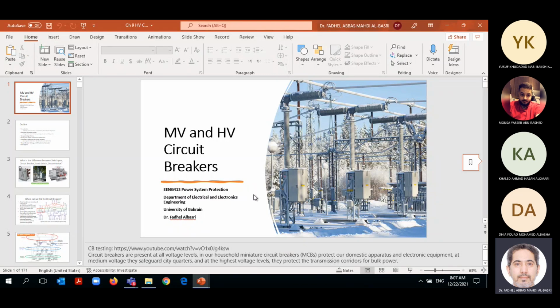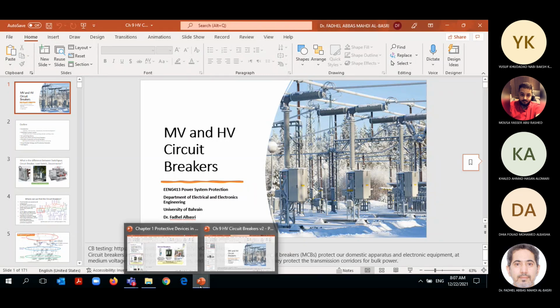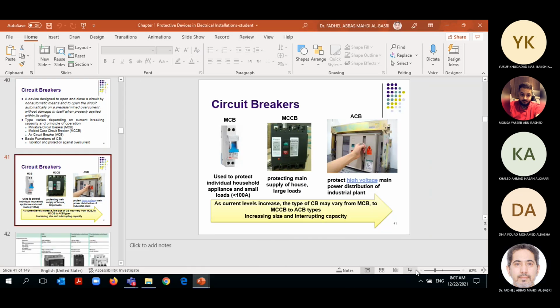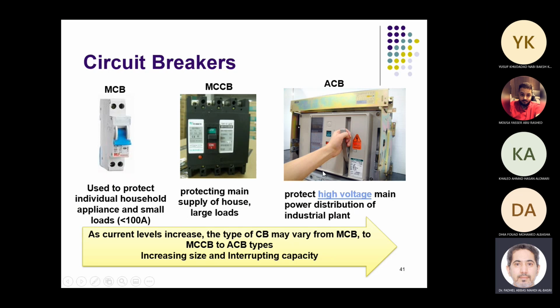So I'll not look at the breakers that are at home, like these ones. These are the breakers at low voltage systems. They classify them from low: MCBs, which we call miniature circuit breakers. Miniature means small breakers, and these breakers are normally rated up to, let's say, 100 ampere. This is for household circuit protection, and you'll find it in a distribution board that I'll show you later. Their breaking capacity, the maximum current that they break, is also limited to, let's say, 5 kiloampere.